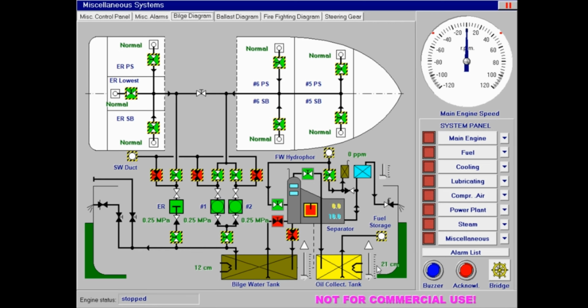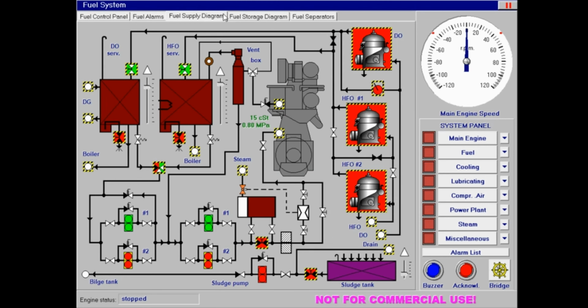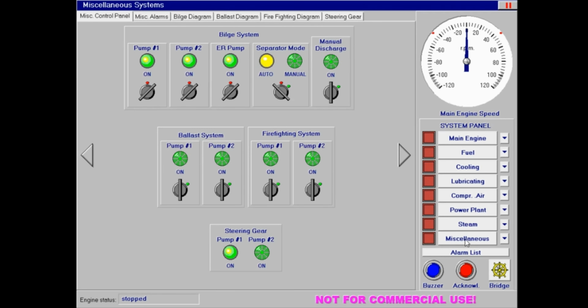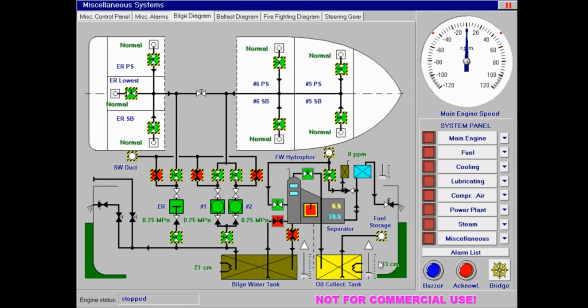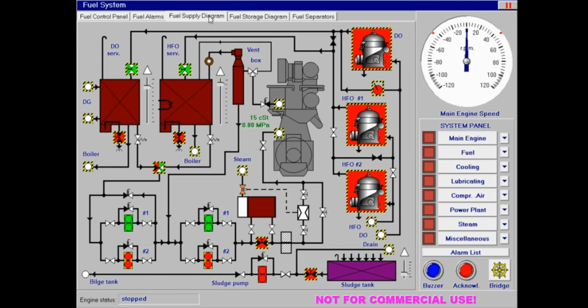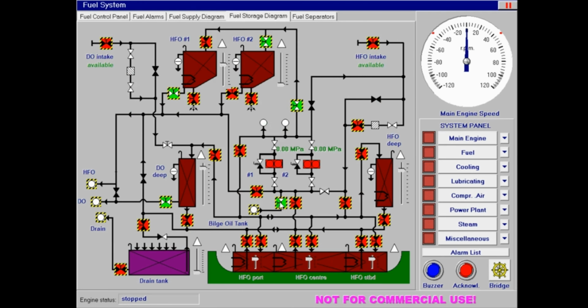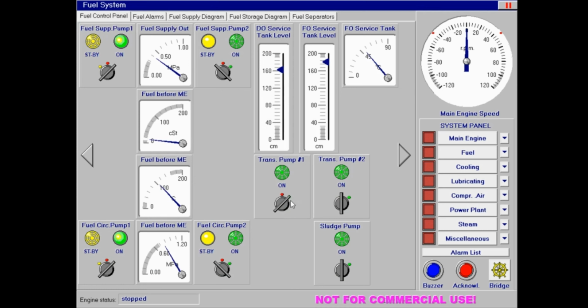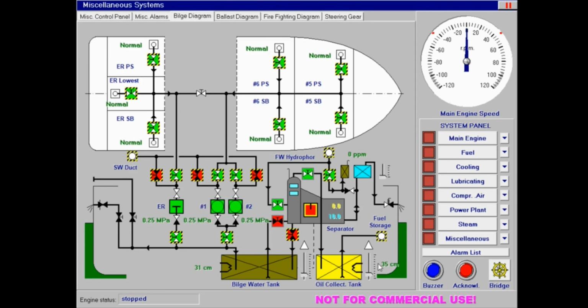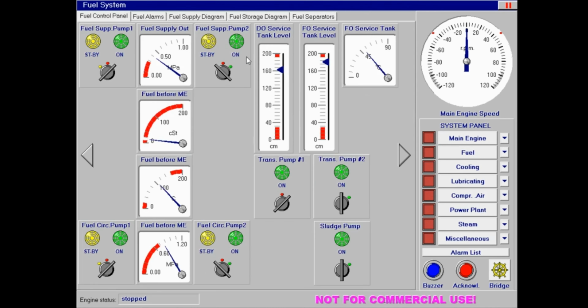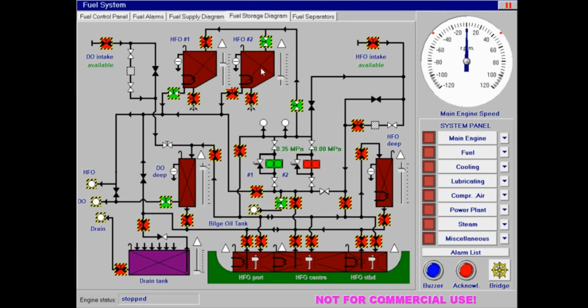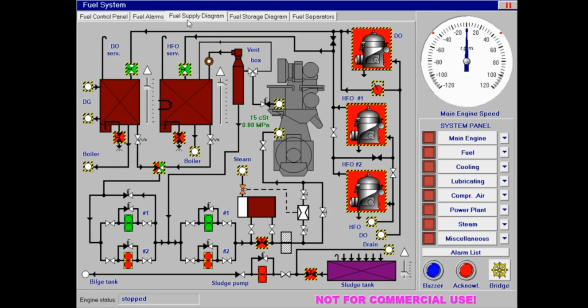And now we can start pumping fuel to the HFO tank from the oil collection tank or from the separator. To do that, we must open the inlet valve and the fuel transfer pump valves and start the transfer pump. And as you can see, the level is dropping since it is being transferred to HFO tank number 2. So for now, we must close these valves, shut off the transfer pump, open the sludge tank suction valve, and start the sludge pump.